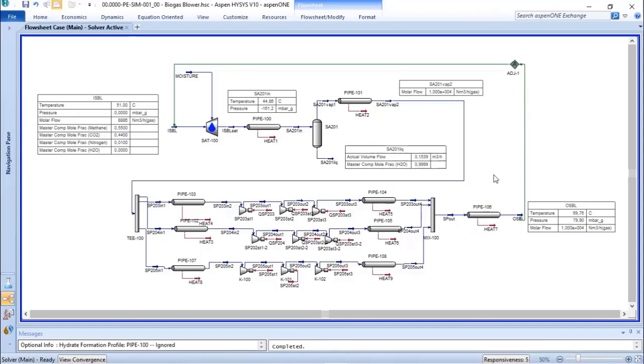Before we update our process flow diagram, I need to remind you that we kept the pressure ratio constant, so we can verify that the temperature remains the same at the blower's discharge, and the discharge pressure decreased, because now we have a lower suction pressure with a constant pressure ratio, we will have a lower discharge pressure. In order to fix that, we need to calculate the new pressure ratio and set that in the blowers. You can see the equation on the screen and the result of the calculation there.